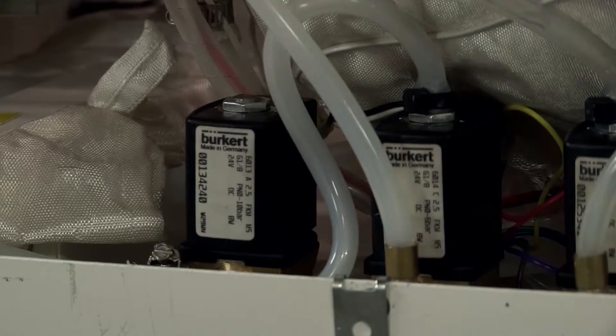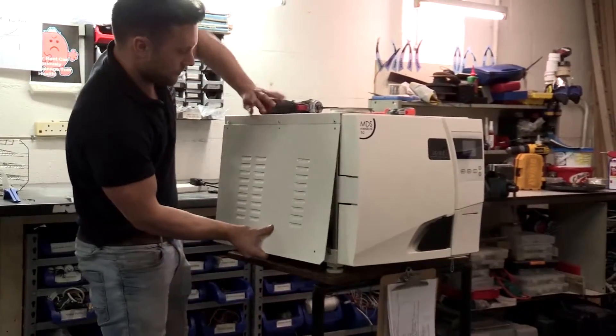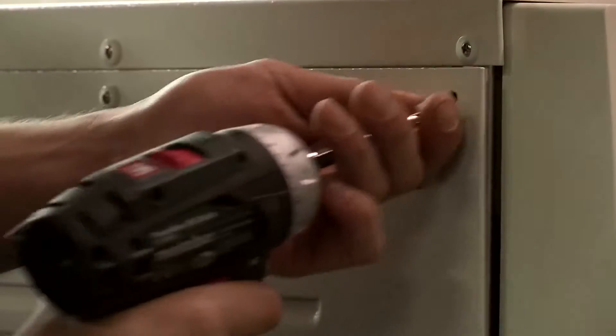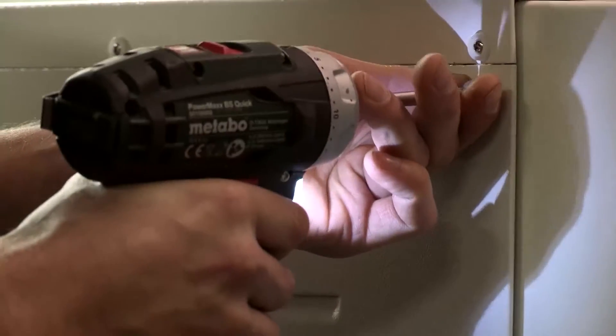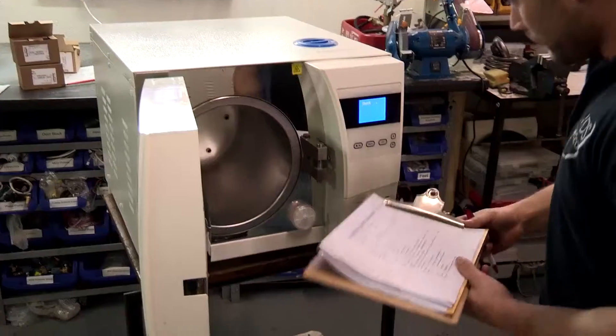Depending on the duty we say to the dentist every six months we should be servicing your machine. But what we're finding with this particular valve is we could probably go for two years without even changing anything on that valve or even more.